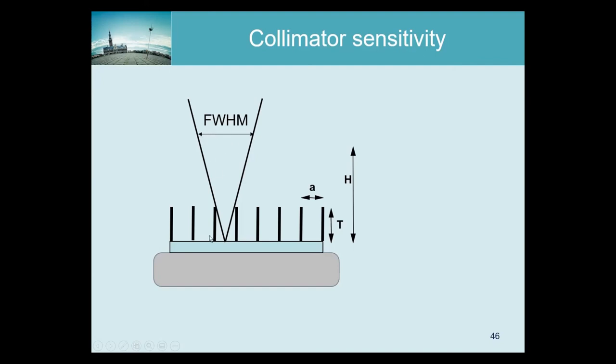Now, the gamma camera is approximately shift invariant. So that means moving the point source from left to right is equivalent to moving the gamma camera from left to right, or considering other parts of the gamma camera. So I could redraw this drawing by making the same drawing here.